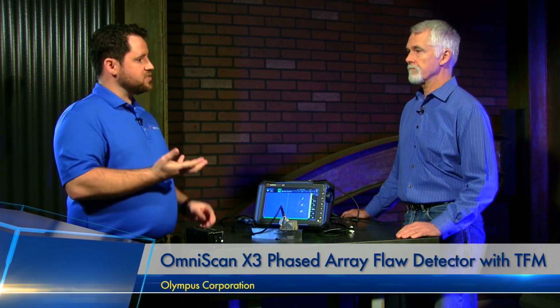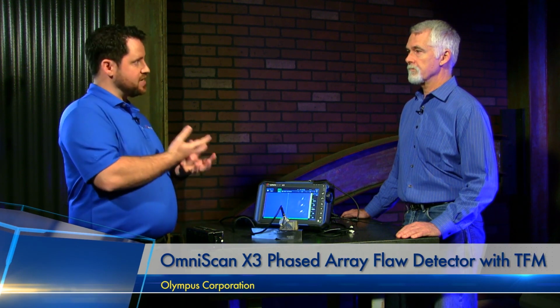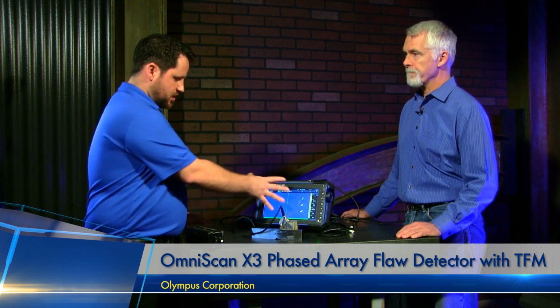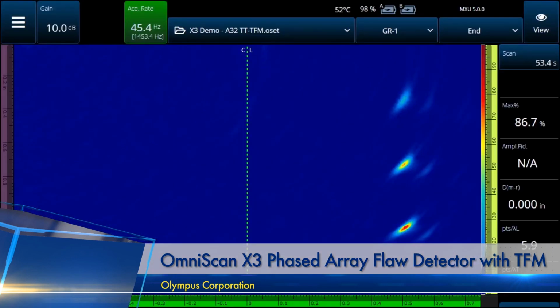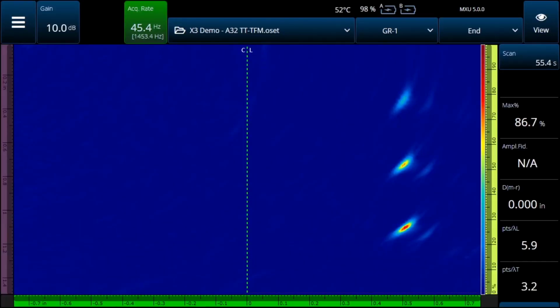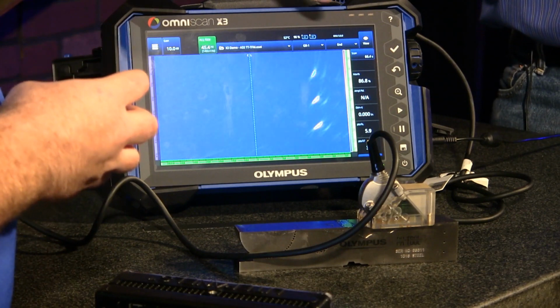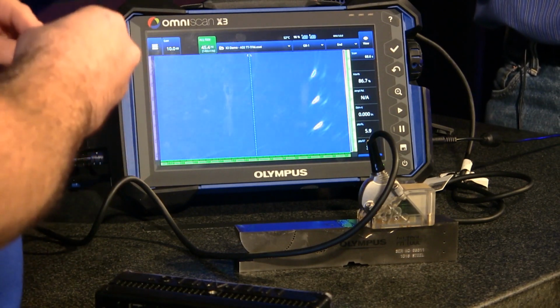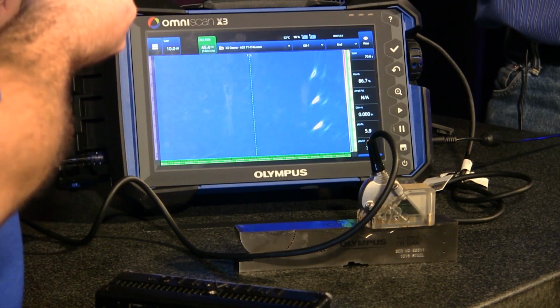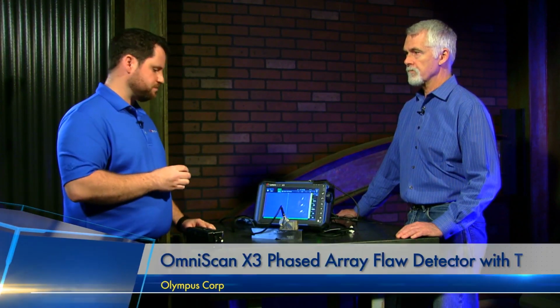What the TFM does, the total focusing method, is it takes that data and places it into our image. Okay. And the image, which you're seeing on the screen now, is essentially a giant grid. We have grid lines that go across the display. We have grid lines that go up and down the display, as many as 1,024 both across and down. Okay. So a very high resolution capability image. We tell the machine how to calculate the time of flight to each one of those grid points.